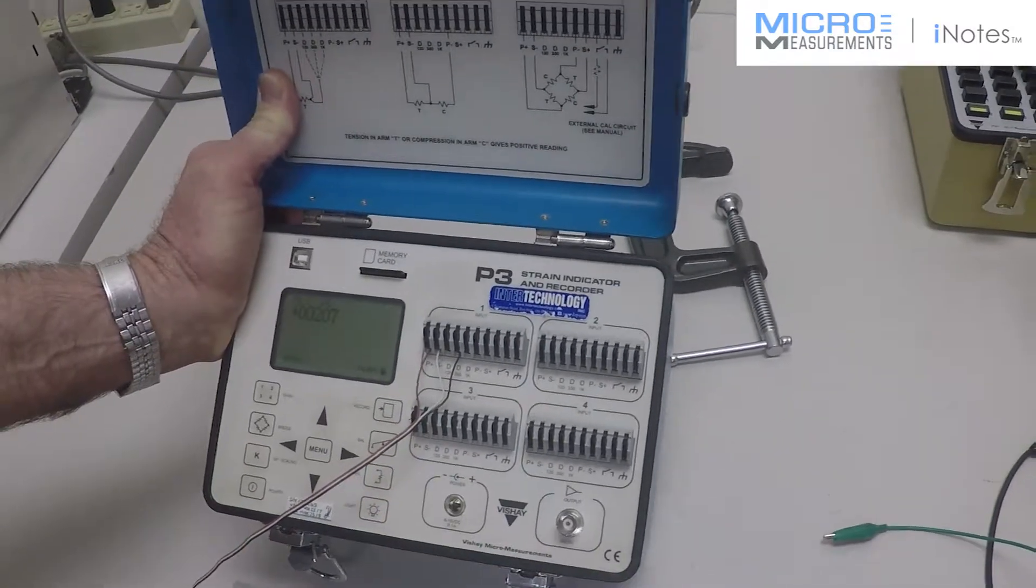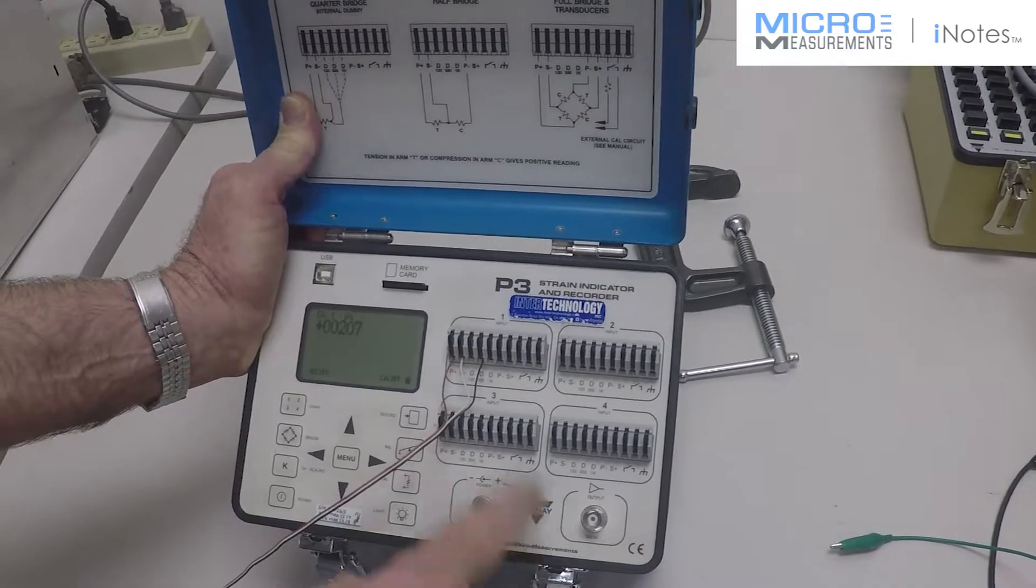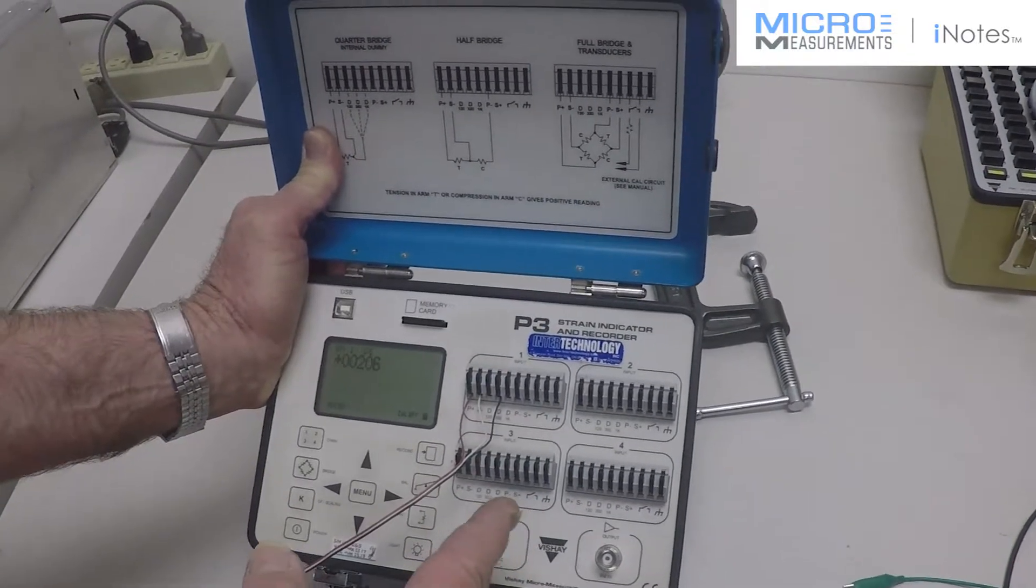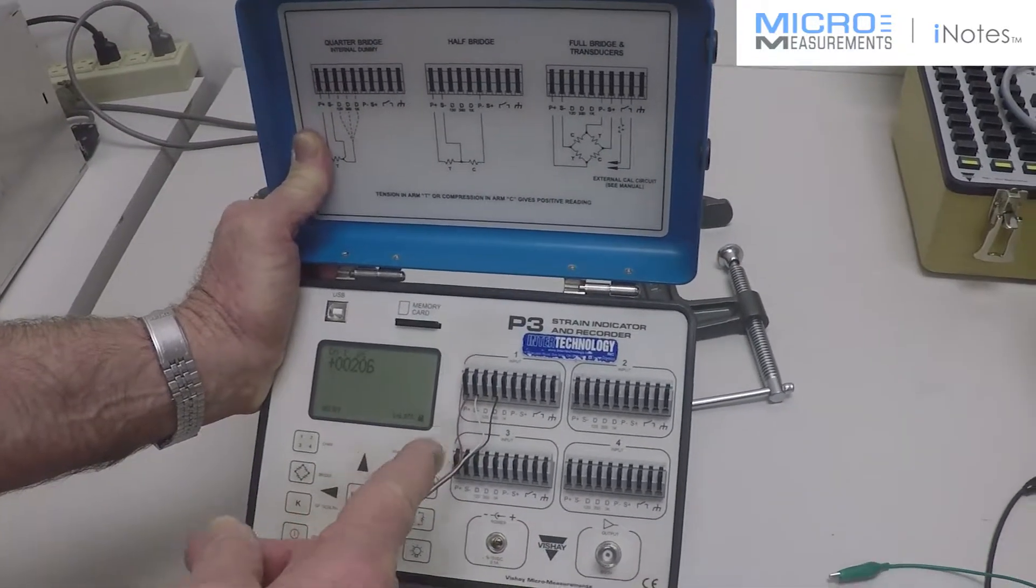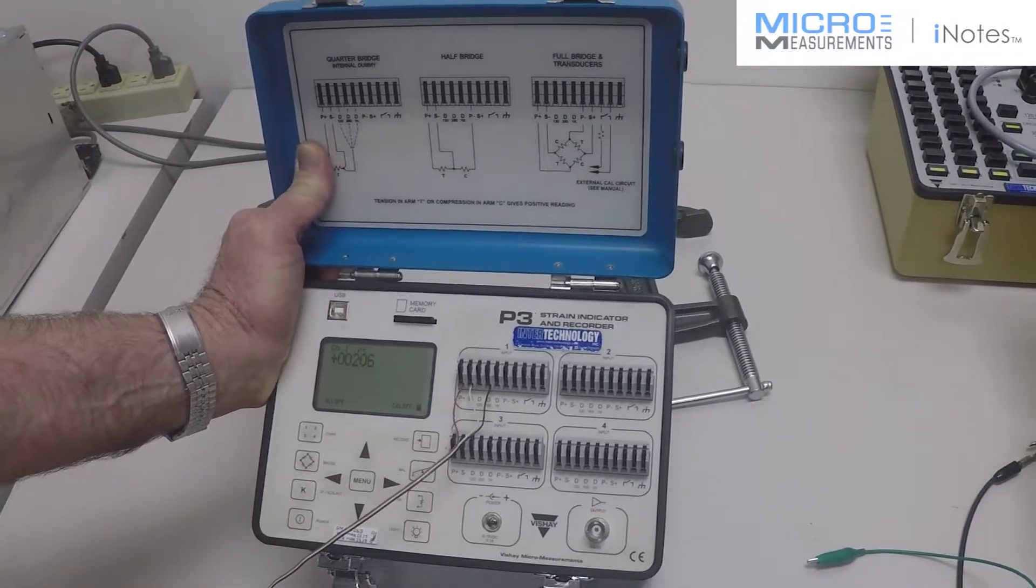We have a quarter bridge here and we have precision resistors built into the unit to complete the bridge, so we can accommodate 120, 350, and 1000 ohm strain gauges directly.